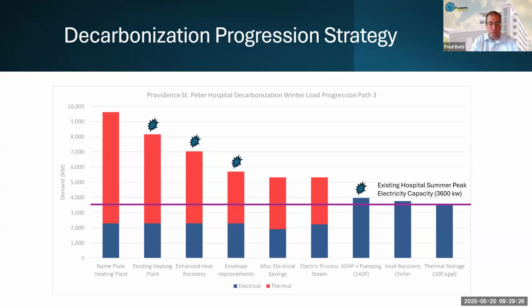So the next thing we look at is what are the big drivers for peak demand in hospitals? First is conditioning outside air. And so there are dozens of air handling units at the hospital, including 9, which make up roughly 50% of all airflow, that are 100% outside air. 8 of those 100% outside air units have standard runaround loops with about a 50% effectiveness, and one of those air handling units has no airside heat recovery. And so what we looked at is retrofitting those with a higher performing enhanced runaround loop that gets an effectiveness around 80%, and with that added heat recovery and replaced heat recovery, we're taking away yet another megawatt of heat demand at peak. And again, this is at peak, not average over the time, right?